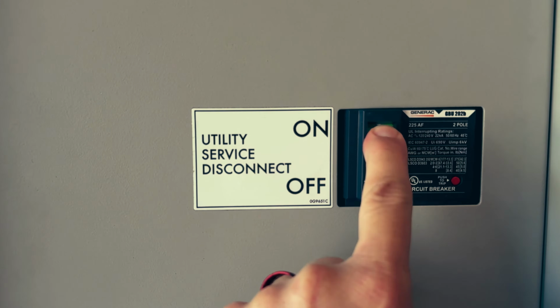Even though your utility power is already out, Murphy's Law says it'll come back the second you start messing with it. So as a precaution, turn the ATS's main breaker off. It's usually at the top right corner of the panel. Now we're ready to manually transfer power to the generator.